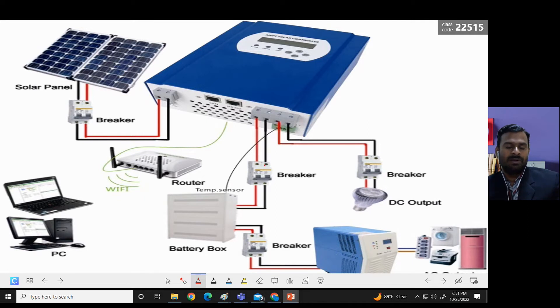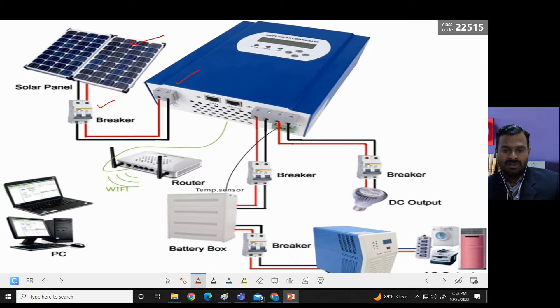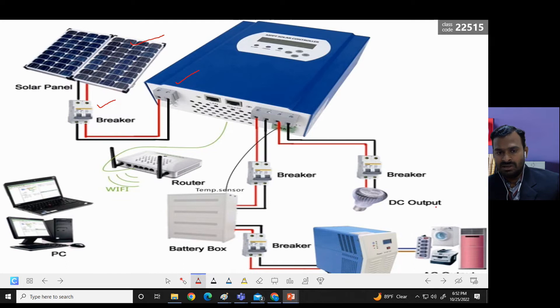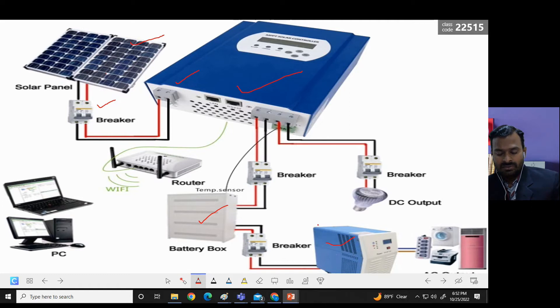This shows the overall system for a solar power setup. We have solar panels connected through a breaker or isolator to the charge controller. From the charge controller, another breaker connects to a battery bank, from the battery bank to an inverter, and from the inverter to AC loads. DC loads can be connected directly to the DC output. The main components in a solar power system are: the panel, protective or isolating devices, a charge controller, a battery bank, and an inverter.